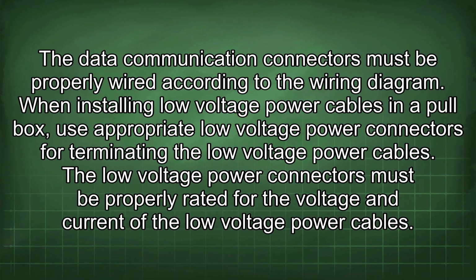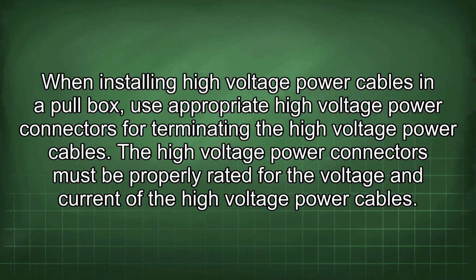When installing low voltage power cables in a pull box, use appropriate low voltage power connectors for terminating the low voltage power cables. The low voltage power connectors must be properly rated for the voltage and current of the low voltage power cables. When installing high voltage power cables in a pull box, use appropriate high voltage power connectors for terminating the high voltage power cables. The high voltage power connectors must be properly rated for the voltage and current of the high voltage power cables.